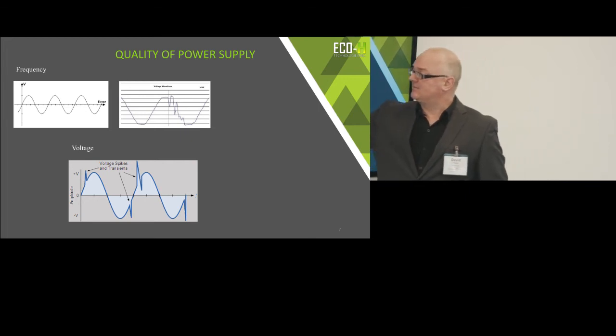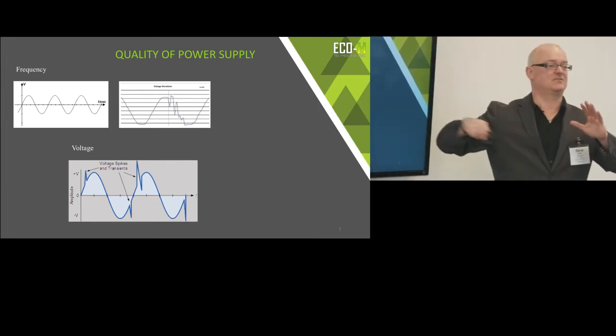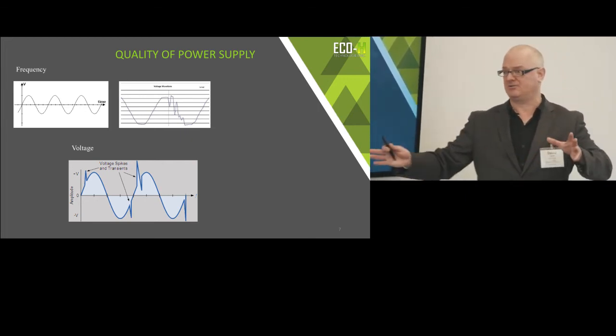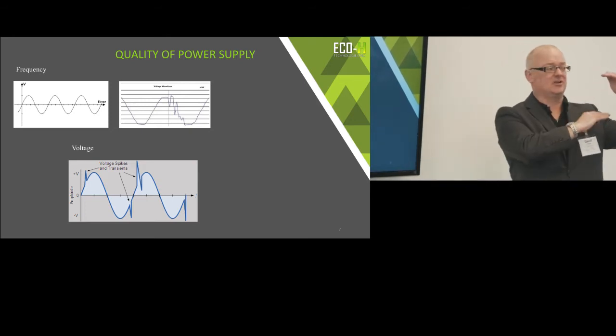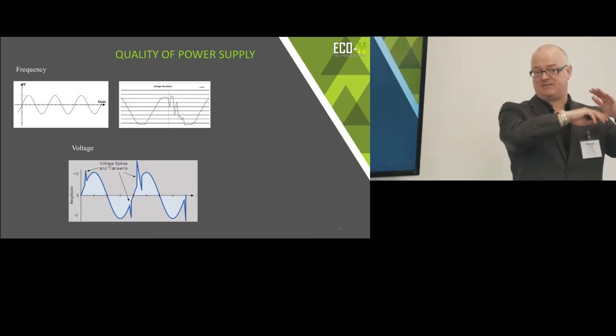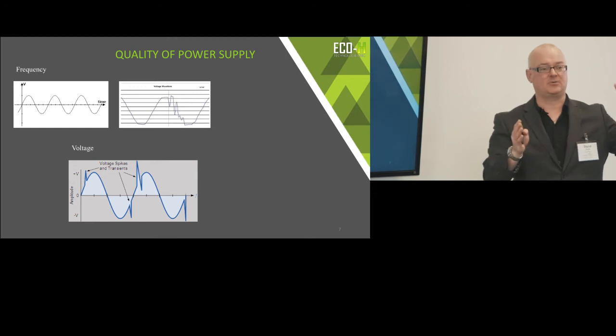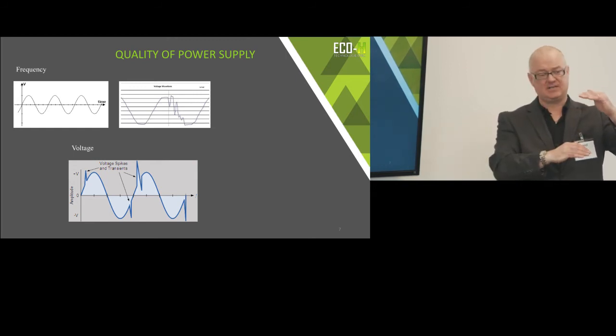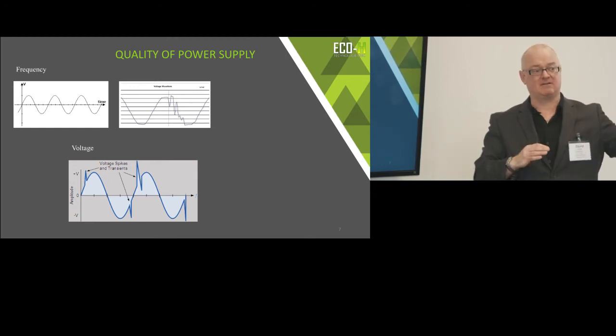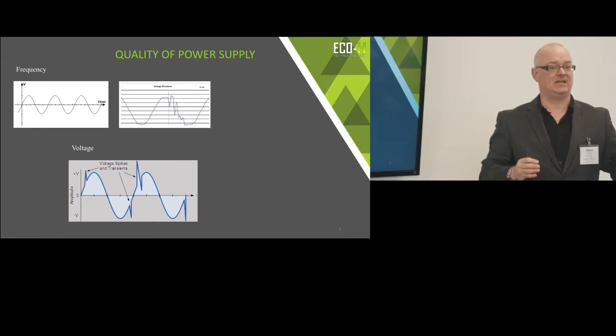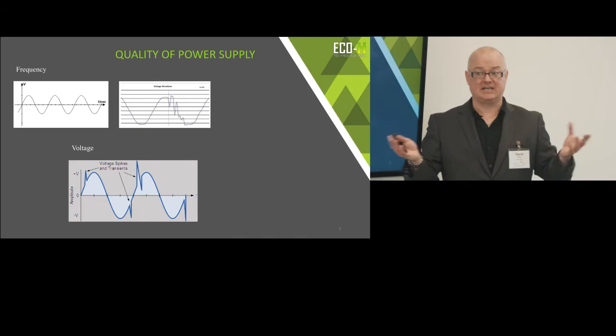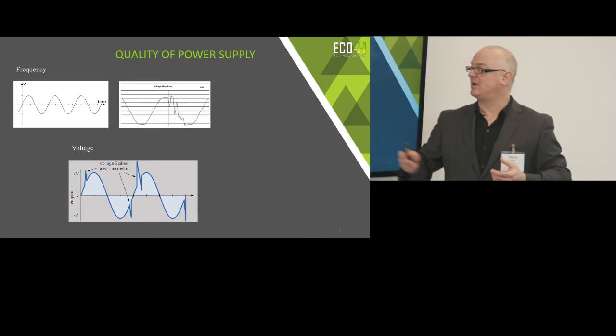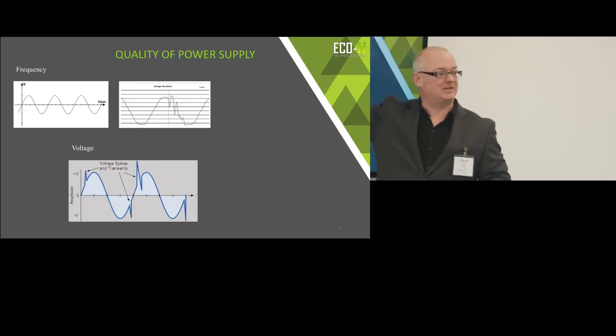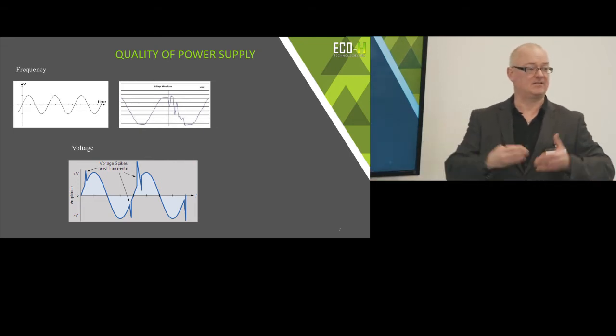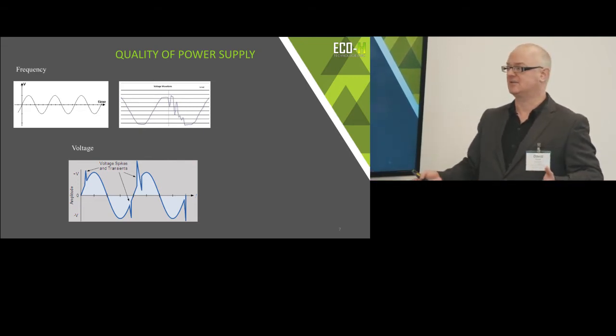So a typical VFD control system runs on a 60 hertz supply, or motor control, or any computerized system, and it has a tolerance of, let's say, 5%. So if that frequency goes up to 65, it'll still operate. If it goes down to 55, it will still operate. If it goes out of that range, then it causes big problems for the actual hardware itself, and the software finds a problem with it. So it kills itself and it shuts down. So there's no way to determine or to predict when these are going to happen, but the result is that things shut down, hardware shuts down, again, to save itself.